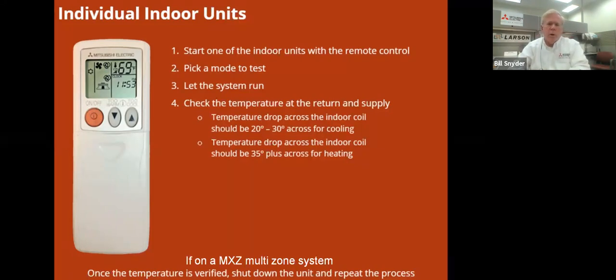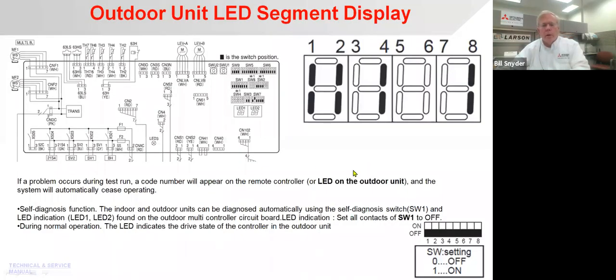And that usually is miswired. So good practice would be to start them up one at a time, and then check the temperature. This is kind of what we call a rule of thumb. Across the indoor coil should be a 20 to 30 degree temperature drop for cooling, and a temperature rise, this says drop, but a temperature rise of 35 degrees across the coil for heating, is right around what we would expect to see if it is charged properly.